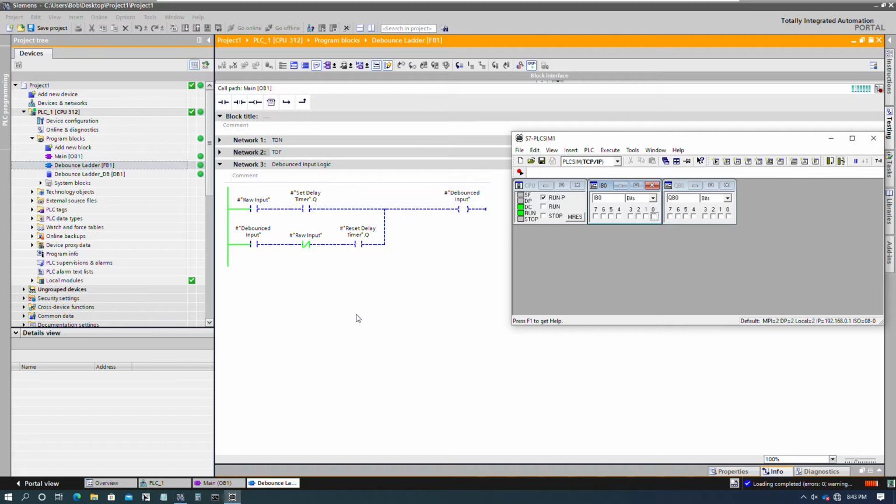So let's take a minute and talk about RLO. This is in the Siemens ladder manual and in the STL manual. If you try to think of RLO as the green power moving down the rail here, or along the rung, we've got power coming into this raw input, but because our contact isn't closed, our RLO drops past it. We've also got this parallel branch, and we've got power coming in, but because we don't have debounced input, everything is dropped out after that. When we turn on our input, now RLO is made, and once our timer is made, it'll allow it to continue. And then this output right here takes the RLO and writes it to this variable right here.